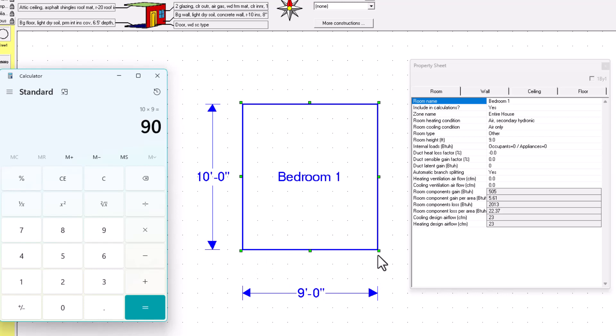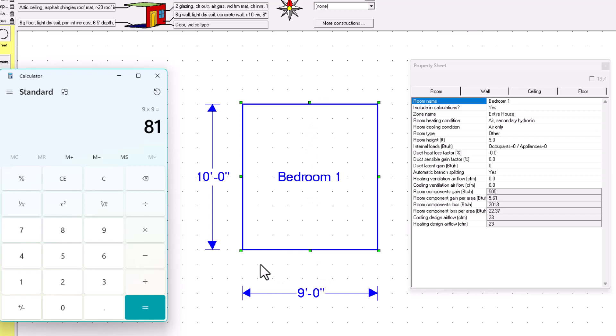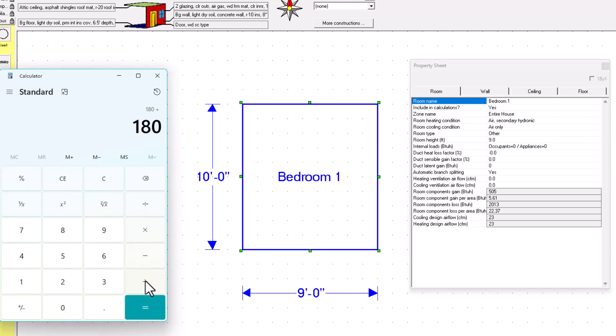The other two walls are 9 feet long at a height of 9 feet, so 9 times 9 equals 81. We have two of those walls, so 81 times 2 equals 162. Adding them together: 180 plus 162 gives a total exposed wall area of 342 square feet. It's always important to know how the calculation works.